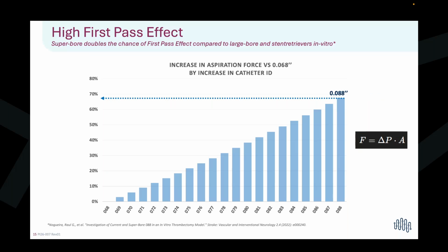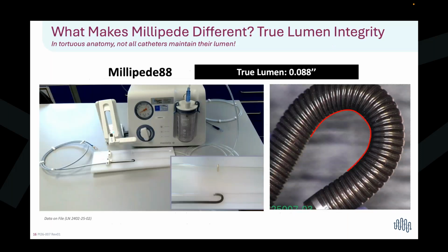With regard to the larger catheter, we know that there's a significant increase in aspiration force by catheter internal diameter because force equals the difference in pressure times the cross-sectional area of the catheter. And so there's a relatively linear increase in the ability to create aspiration force depending on the cross-sectional area of the catheter, which increases by the internal diameter.